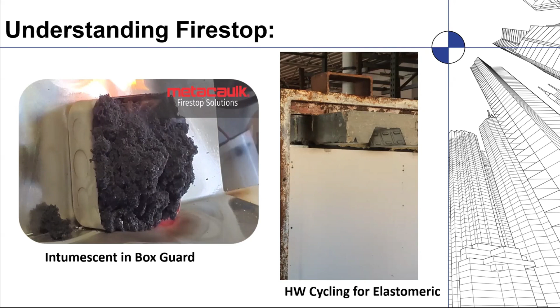One common misconception in the fire stopping industry is that the fire stop material—whether a red sealant, a spray material, or some kind of tape or strip—is a fire stop or fireproof material by itself. But that's not really true. It is one component of the overall construction, which includes the fire stopping material, the penetrating item like a pipe or electrical box, or a joint opening, and the construction of the wall or floor itself, whether concrete, wood, or gypsum.